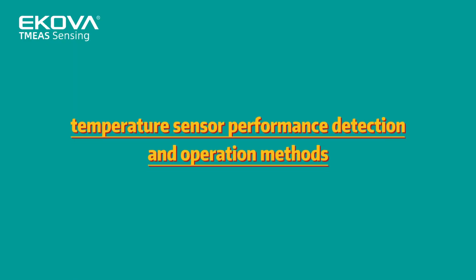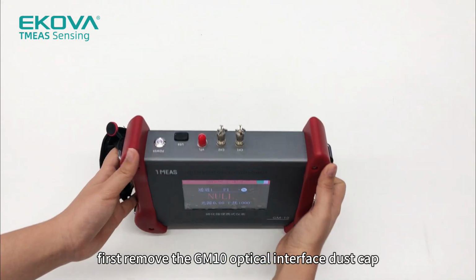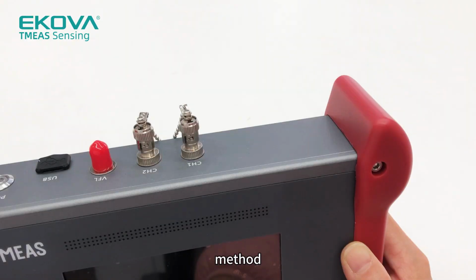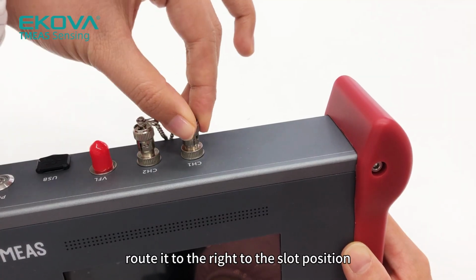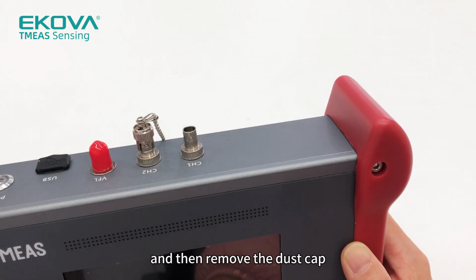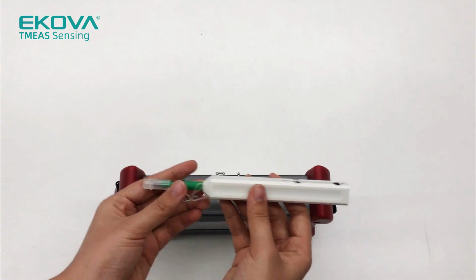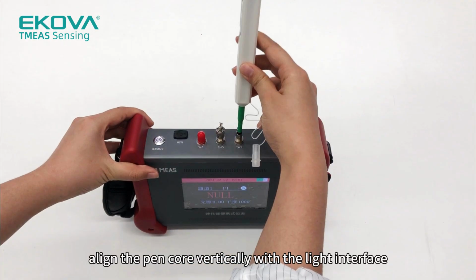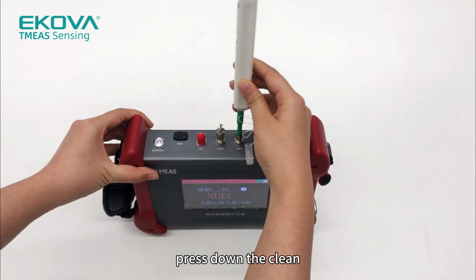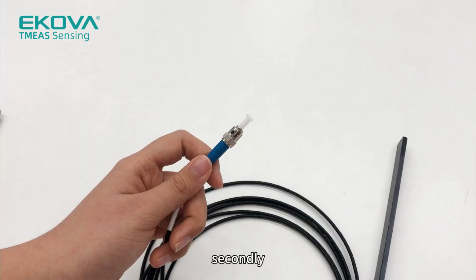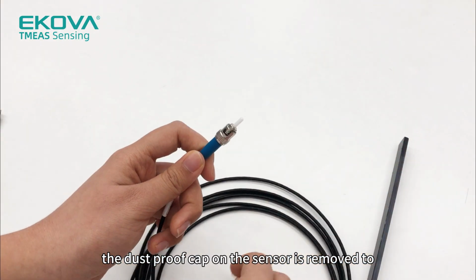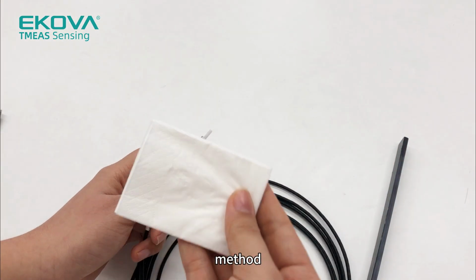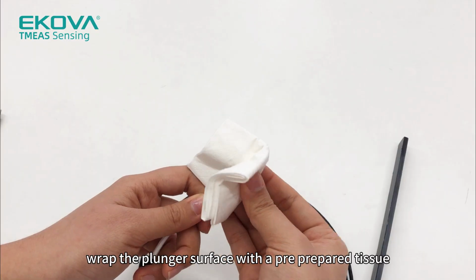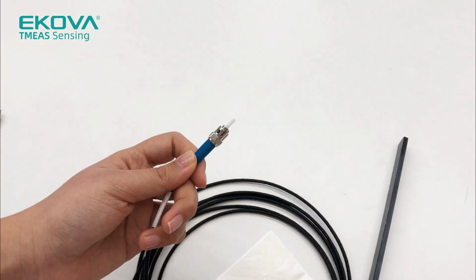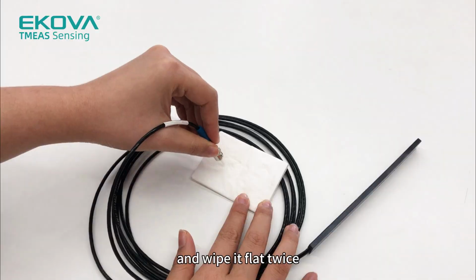The second is temperature sensor performance detection and operation methods. First, remove the GM10 optical interface dust cap. Method: press down on the dust cap, rotate it to the right to the slot position, and then remove the dust cap. Clean the optical interface. Method: use the cleaning pen. Remove the pen cap, align the pen core vertically with the optical interface, press down to clean, and repeat twice. Secondly, remove the dust cap on the sensor to clean the core cylinder and end face. Method: rub the plunger surface with a pre-prepared tissue and rotate, and wipe it twice. Then place the plunger end face on the tissue and wipe it flat twice.